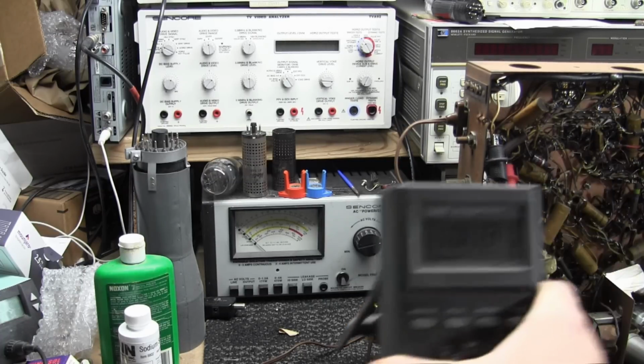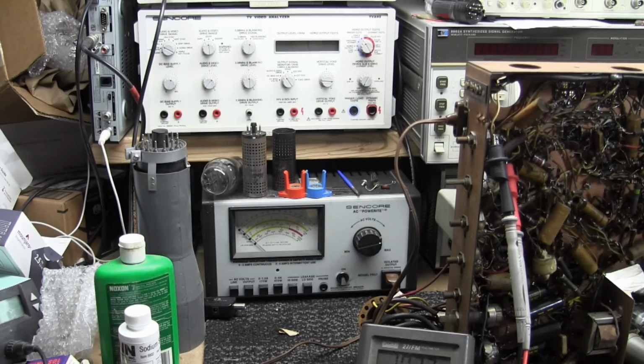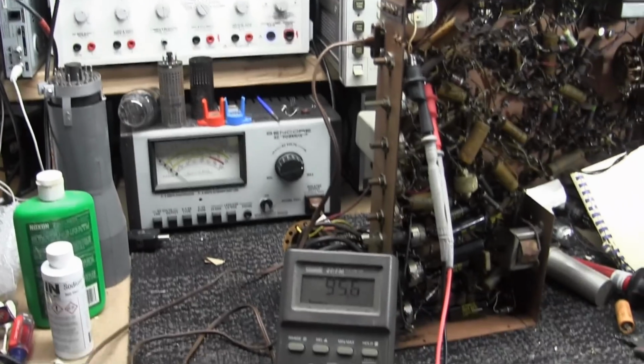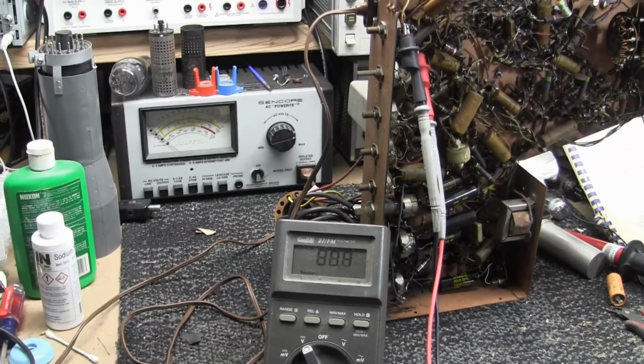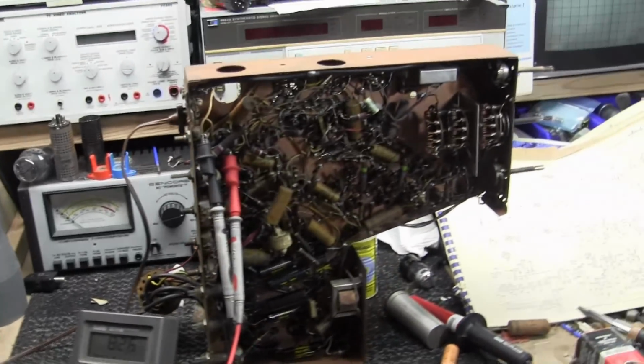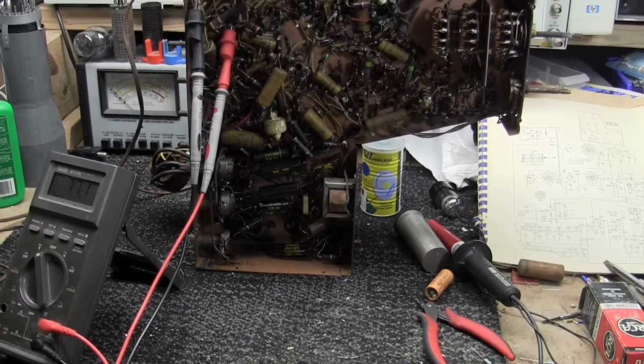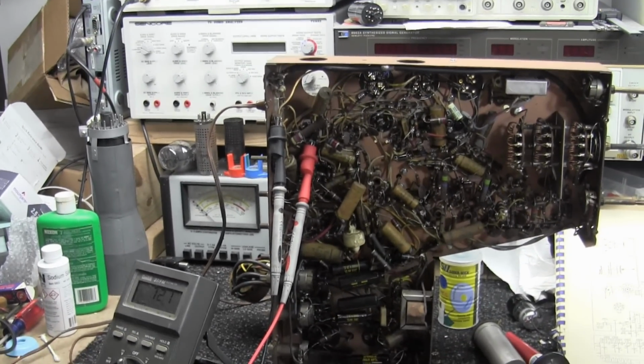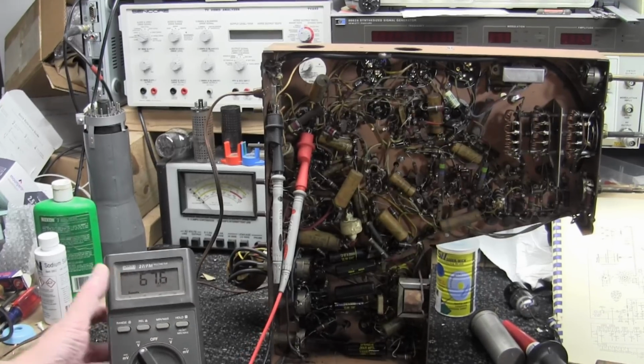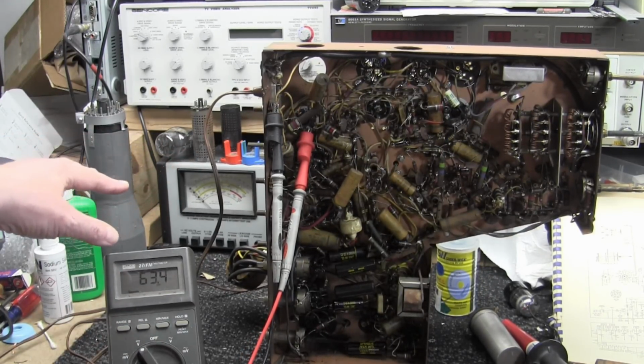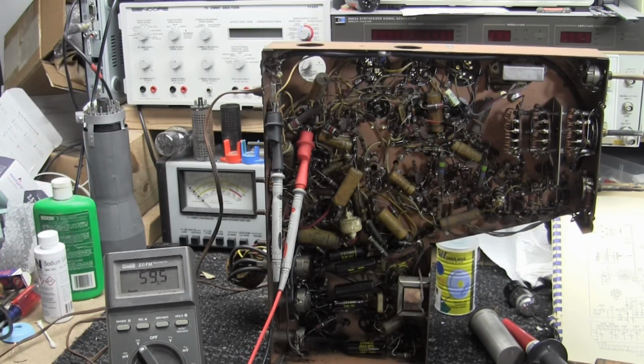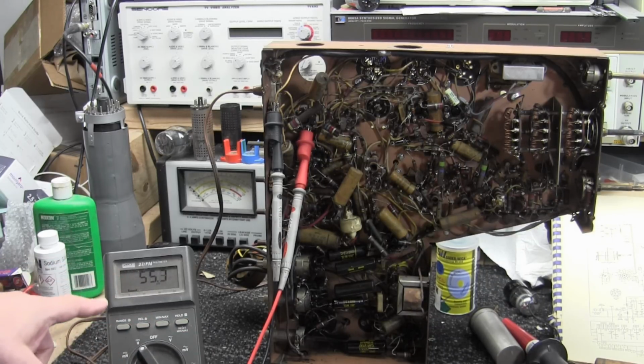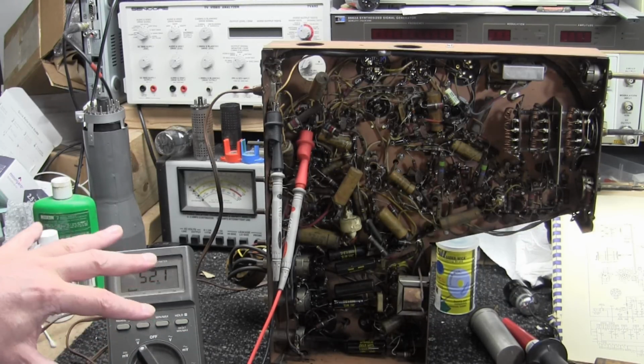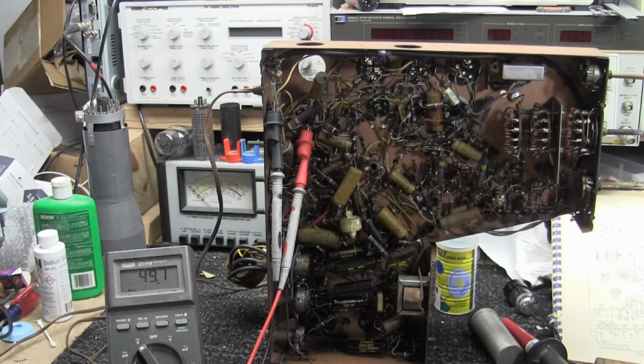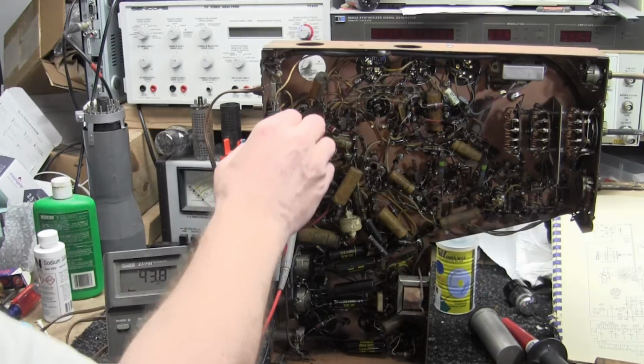In fact, I still am reading over 100 volts on my meter with the set turned off as the caps are slowly discharging. So, this is where your troubleshooting skills come into play. When it's a dead short, it's obvious. The circuit breaker on my supply would have immediately tripped. The meter would have pegged over, and we would have had 0 volts here or close to it. But we had like 2/3 of what we should have. So when we have a dead short, what we have is excessive current draw.